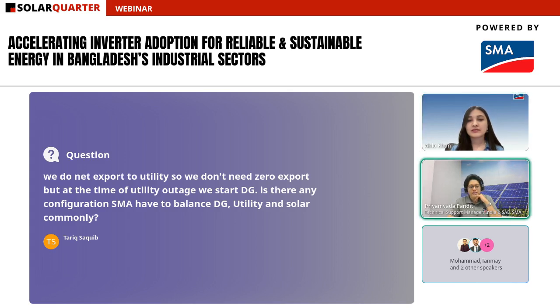So typically what happens in such cases is we take a feedback from the grid. Whenever the grid is available, whatever higher generation you have is exported to the grid. When the grid goes off, the hybrid controller takes over and gives a command to the solar for how much is the generation. As long as the grid is there, it will not give any power limitation commands to the inverter to limit the solar generation. But as soon as it senses that the grid is off and only diesel generators are running, it will actively monitor the diesel generator generation and the load, and accordingly give commands to PV to ensure smooth operation. So this configuration is possible with the hybrid controller.